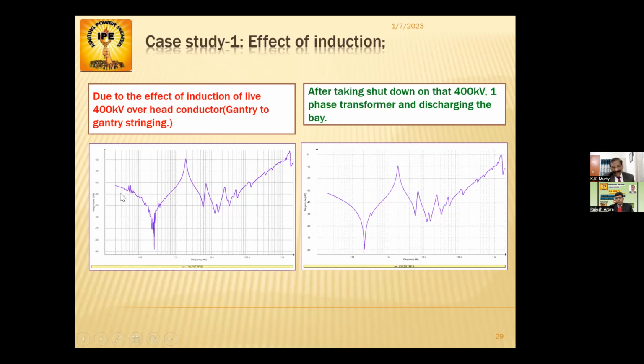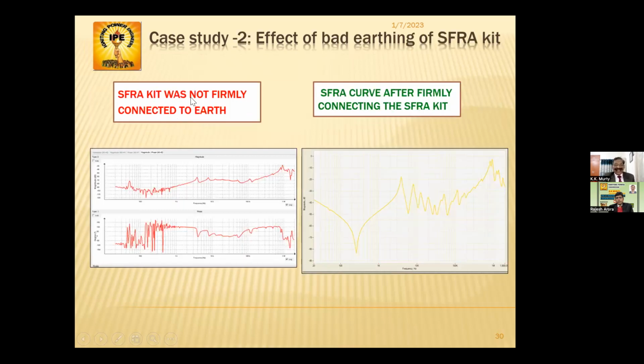Close in the vicinity of the affected induction area. So this is the next one. SFRA kit was not firmly connected to earth. Okay, so the curve was like this. You can see the distortion. This is the SFRA curve after firmly connecting the SFRA kit to earth. So you can see it is a smooth curve here. So this is the number 2 case study.